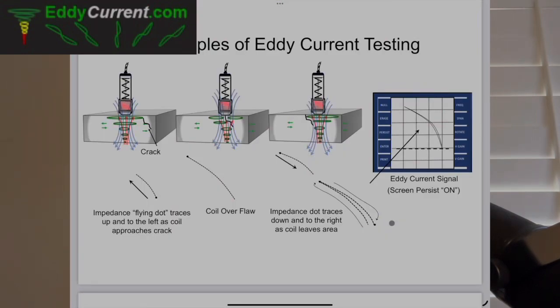When impedance planes are used as tools to explain what happens to signals, their intention isn't to show you what the signal looks like. The intent is to show you how test coil impedance will change for different conditions. A signal is a series of changing impedance values. Think back to the vector points — if you were to connect all those dots, you'd have a squirrely looking signal, but you need all the individual impedance points to make a signal. With an absolute surface coil like in a pencil probe, that surface break notch signal curving up and to the left is maybe a series of a few hundred impedance points, all connected by vectors. Your test instrument is really just an electronic chalkboard displaying the path that individual impedance points are taking.